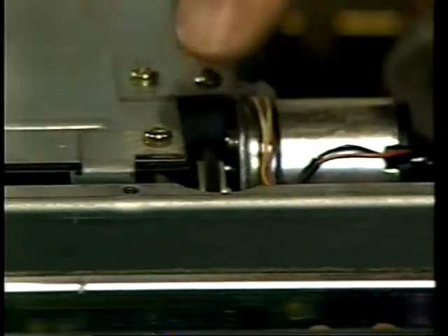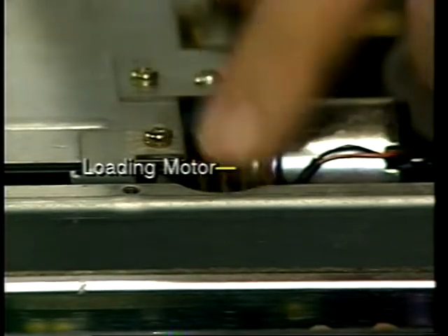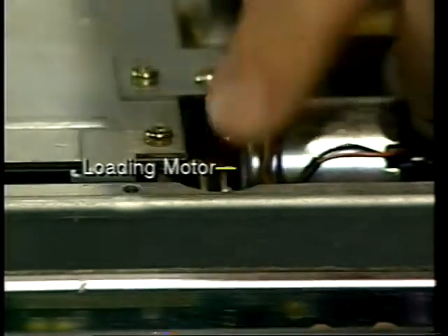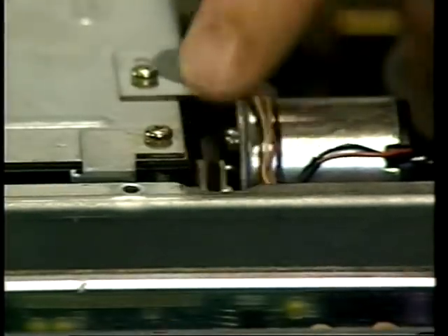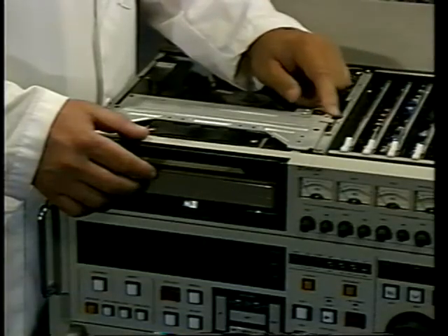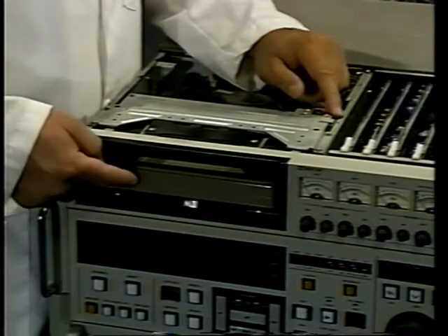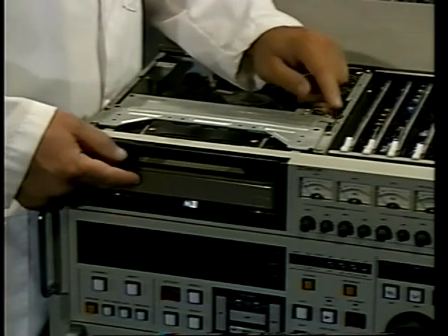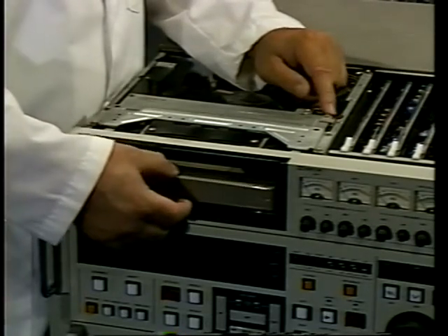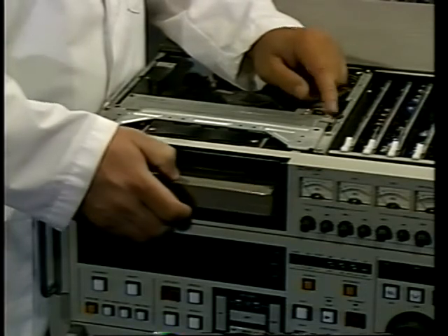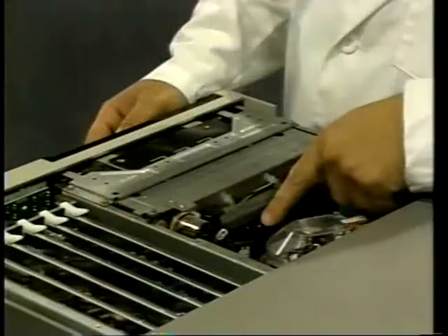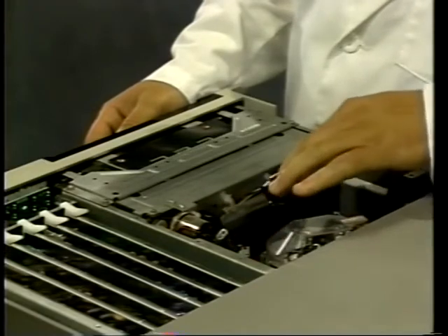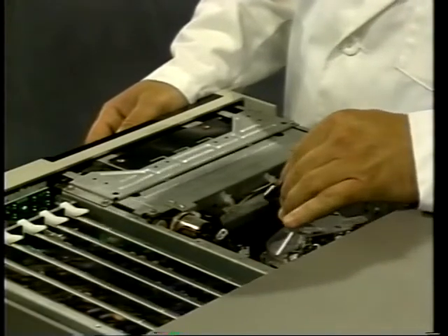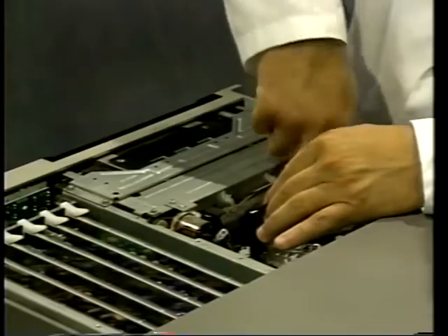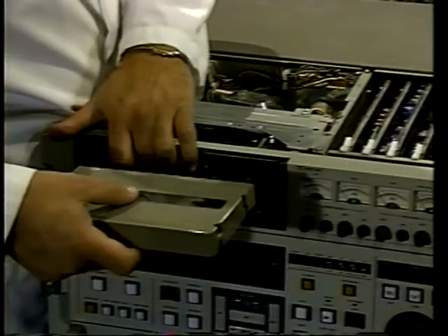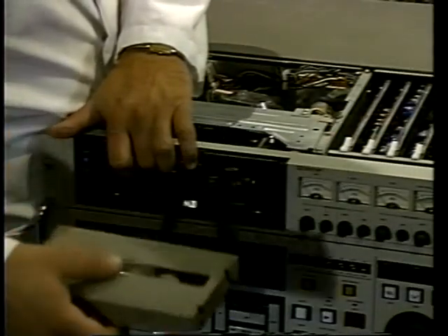Locate the loading motor. Start to wind the loading motor to bring the cassette assembly up. This takes time, so be patient. The cassette will start to come out of the machine here. As it starts to come out of the machine, gently pull it out. The tape is piled up here, and we need to get it out of the machine. Pick up the tape, making sure it is free and clear.